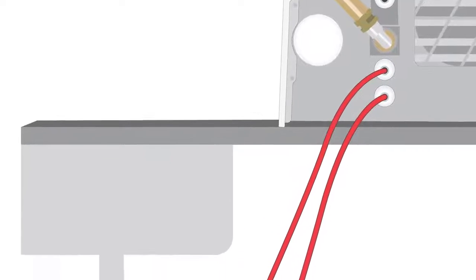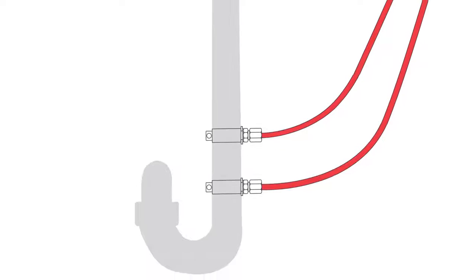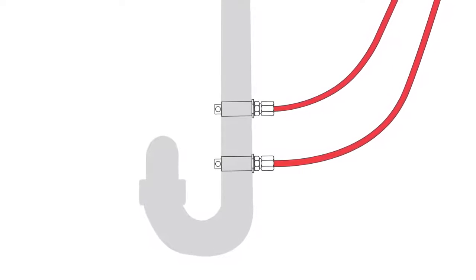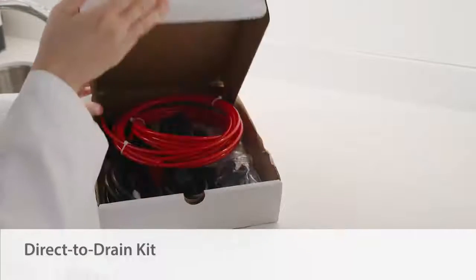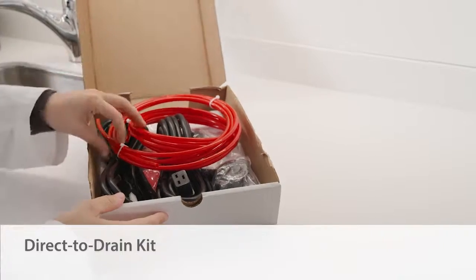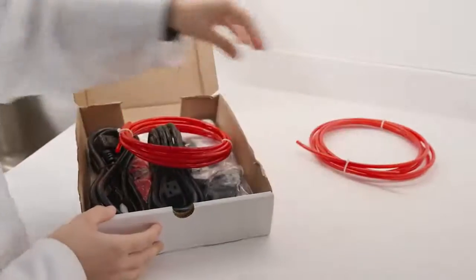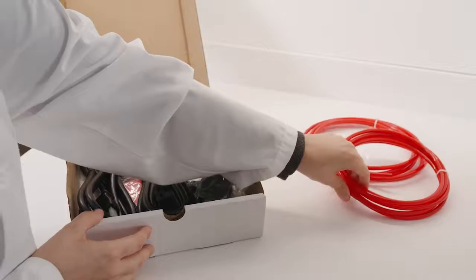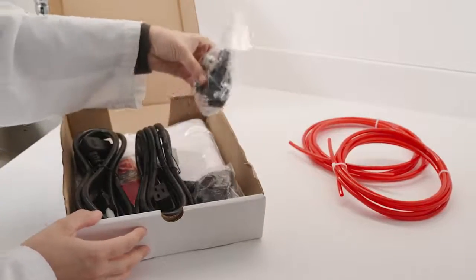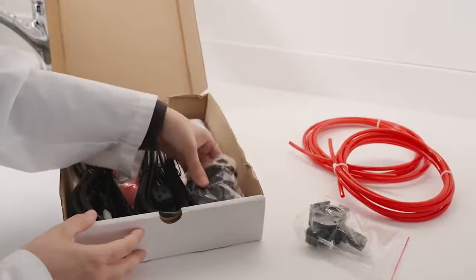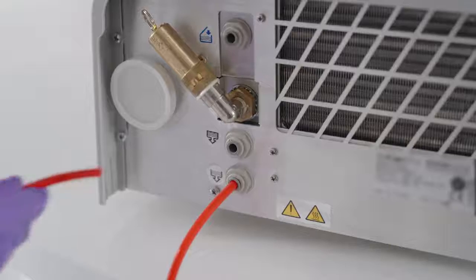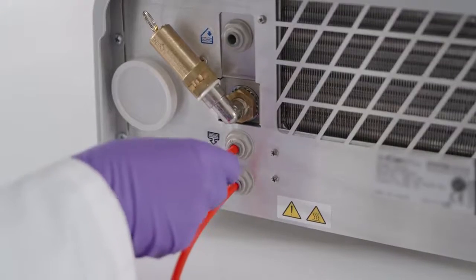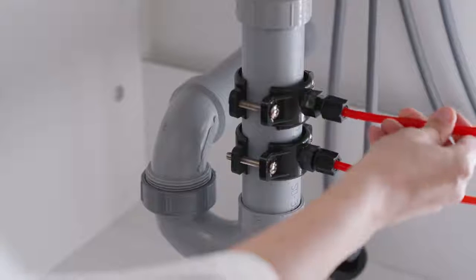The recommended draining setup for the STATIM B is to connect the exhaust hoses directly to a drain using the direct-to-drain kit supplied with your unit. This will prevent any accidental waste bottle overflows if the bottle isn't emptied regularly. This is also the best draining option to use when you are using an automatic filling system. Any new central drain point installation should be done by a technician.